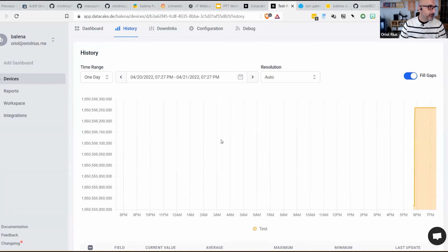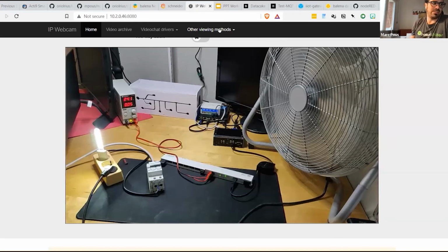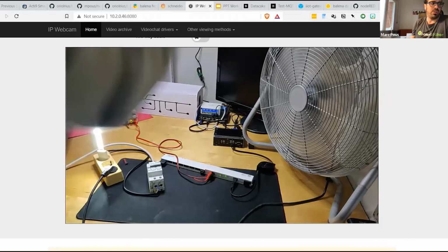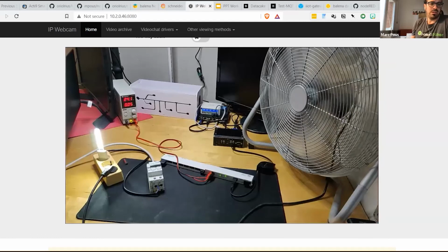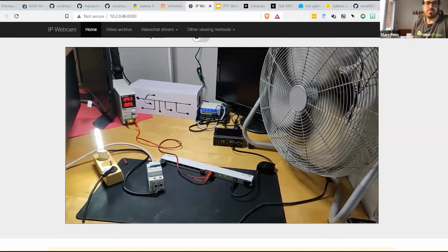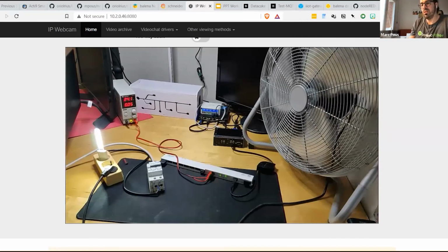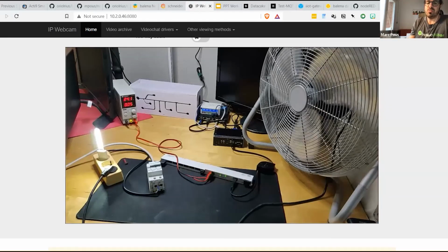Yeah. By the way, the idea is already explained, no? I think so. So what we explained today is how to get into an infrastructure that is running on Modbus, and how to deploy with open source technologies in a really fast time. Actually, maybe it's an extra 20 minutes to deploy everything on an x86 machine. And you're going to deploy different services: NodeRED, MQTT broker, InfluxDB database, and Grafana. And with some simple flows that are actually on the local memory of your NodeRED, you will be able to run something like Oriol showed.